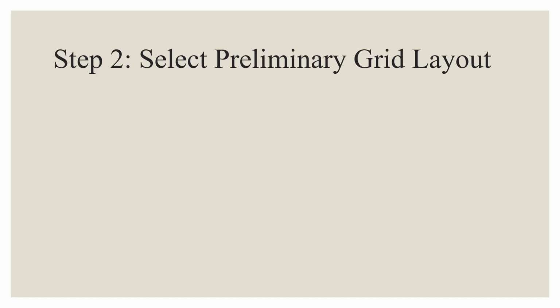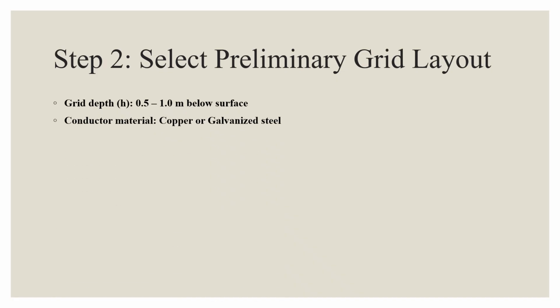So the second step is to select a preliminary grid layout. The grid depth is generally between 0.5 to 1 meter below ground. The grid spacing can vary from 3 to 10 meters depending on soil resistivity and safety requirements. We use copper or galvanized steel conductors and always include a perimeter conductor to maintain uniform potential distribution.